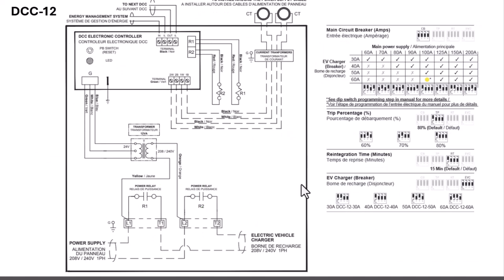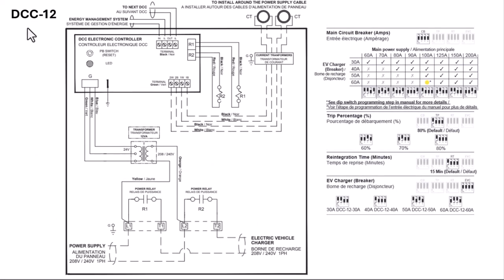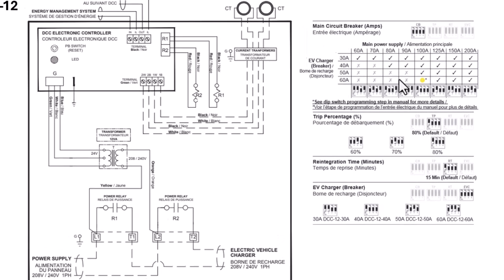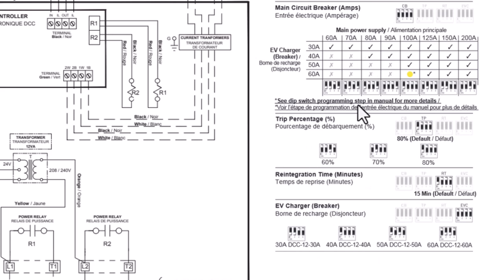And here is the internal wiring diagram of the DCC-12. So this is very similar to the DCC-10, except that the breaker for the EV charger is not part of the box. All right, all you have is the relay and your remote CTs right here, the current transformers, and it'll basically disconnect the power to the electric charger. So the only difference is there is no circuit breaker for the electric charger in the 12 compared to the 10. And with these boxes, there's an adjustment that you can make using dip switches. So you can actually change the trip percentage from that 80% default to 60 or 70% if you'd like.